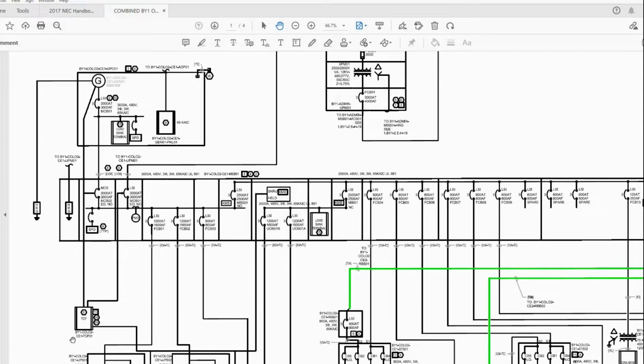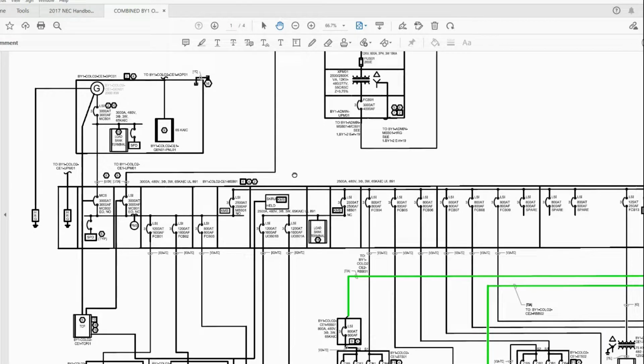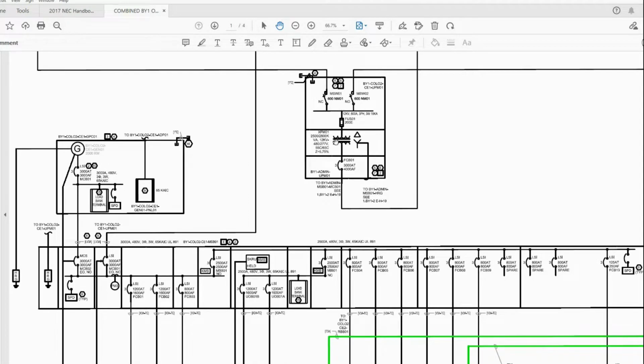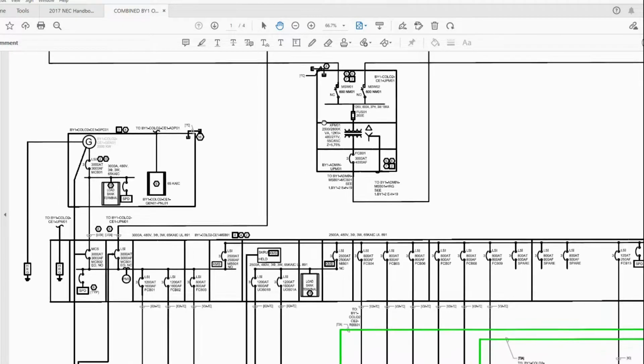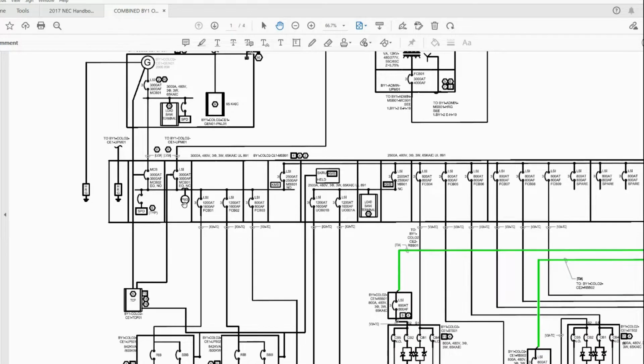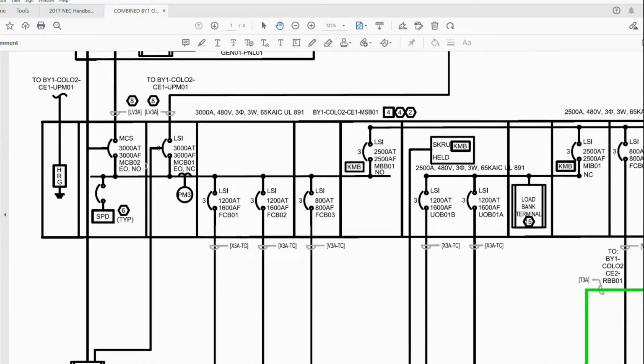Okay, what we got here is a single line diagram showing the MSB, the generator, and our utility feed. Our utility feed is coming through this medium voltage 12 kV to 480 volt transformer. That comes down here into these two main breakers. We have two 3000 amp trip, 3000 amp frame breakers. They both feed along this bus bar right here.